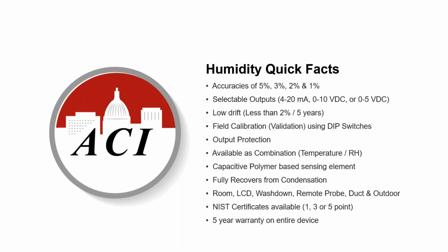We have a selectable dip switch, selectable right on the circuit board, analog output of 4 to 20, 0 to 5, or 0 to 10. We also have a 24 volts AC or 24 volts DC input. So with a lot of our competitors, you can only order a DC with a 4 to 20 or an AC with a 0 to 5 or 0 to 10. Ours is kind of a la carte. It's jumper selectable, all one unit. You don't have to order a specific input or output.